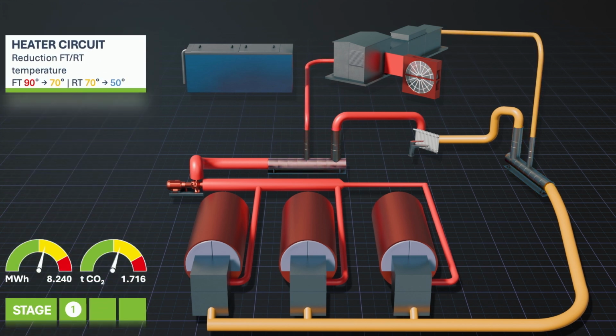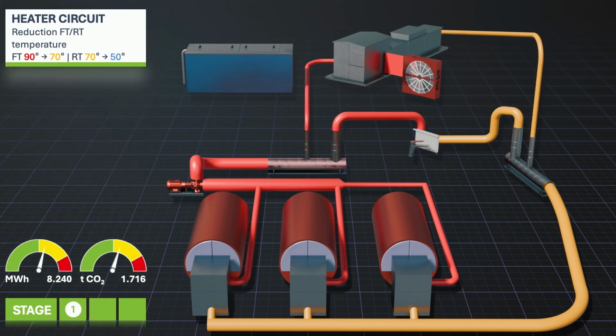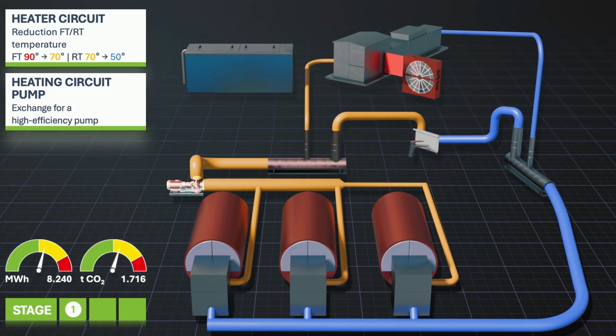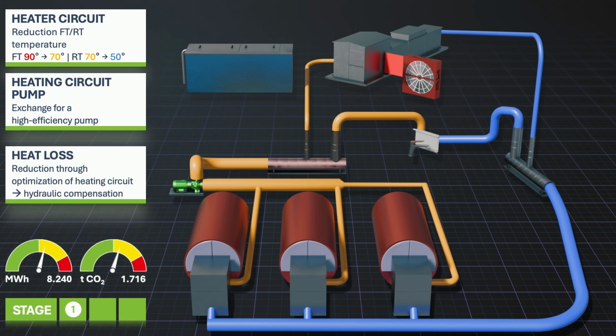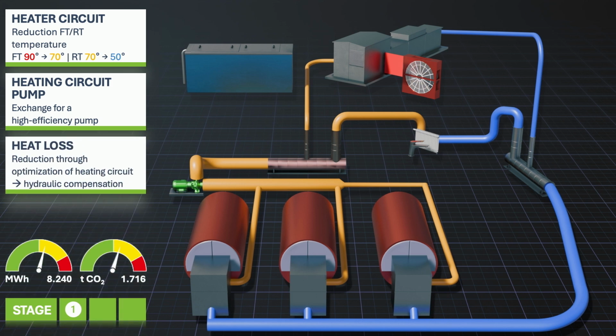As the process no longer requires such high temperatures, the energy requirement in the entire heating network could be reduced. This optimization results in reduced volume flows in the network, and smaller and more efficient pumps can be used. With these measures in the first construction phase, the heat requirement can already be reduced by 40%. However, one thing is crucial for all these measures: converting the hydraulics in the technical center.